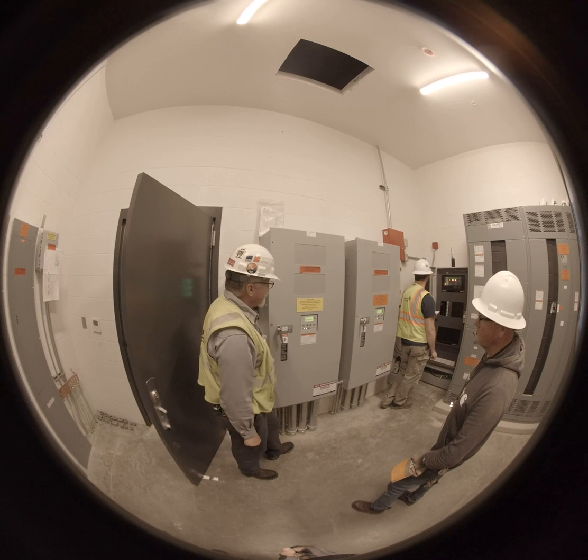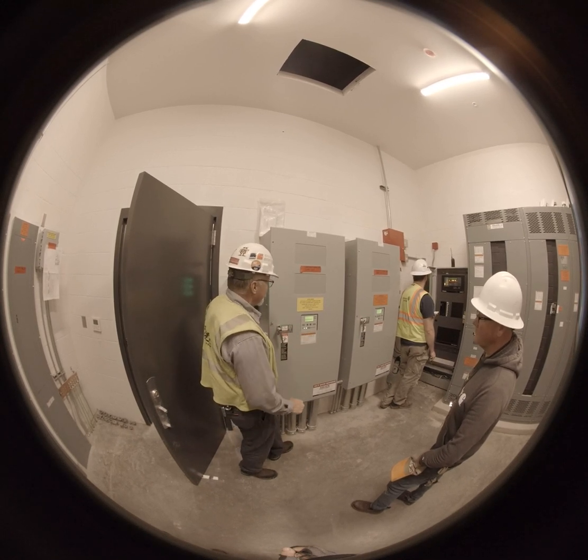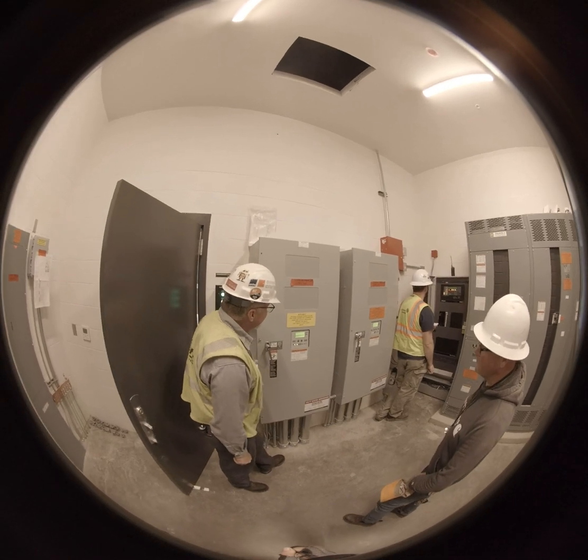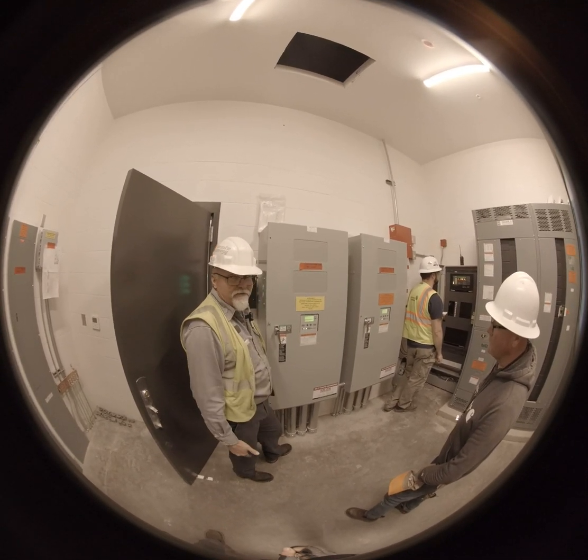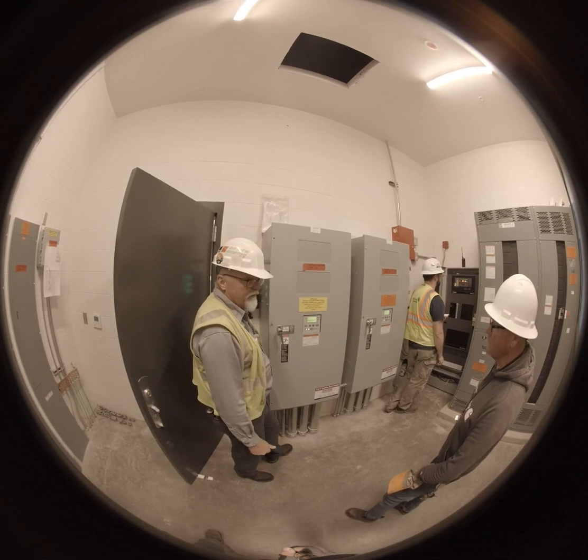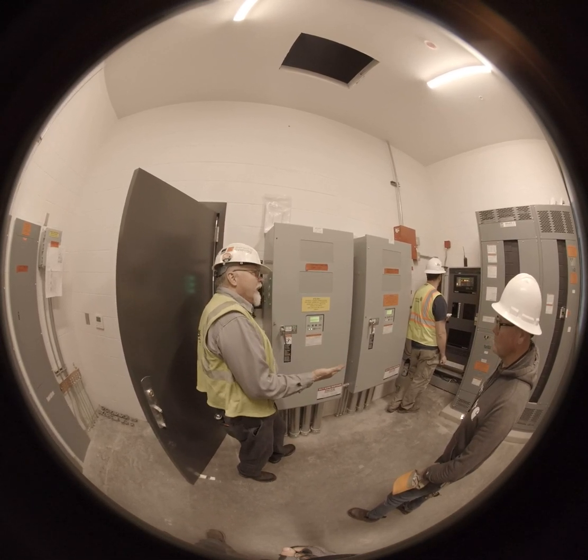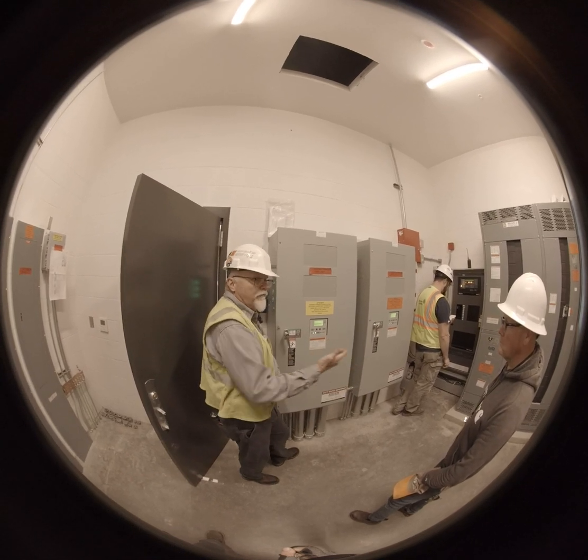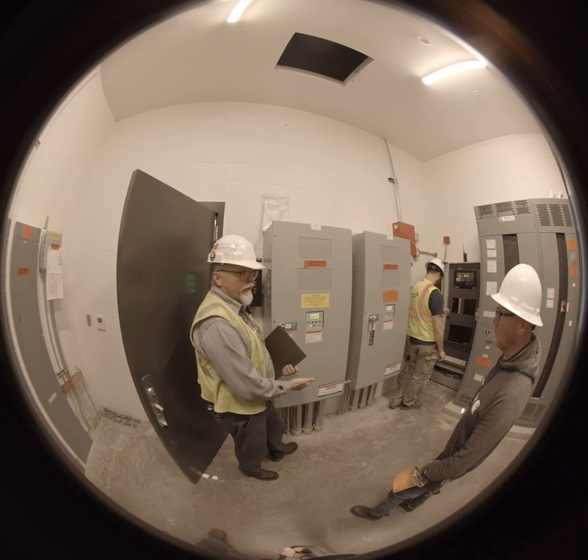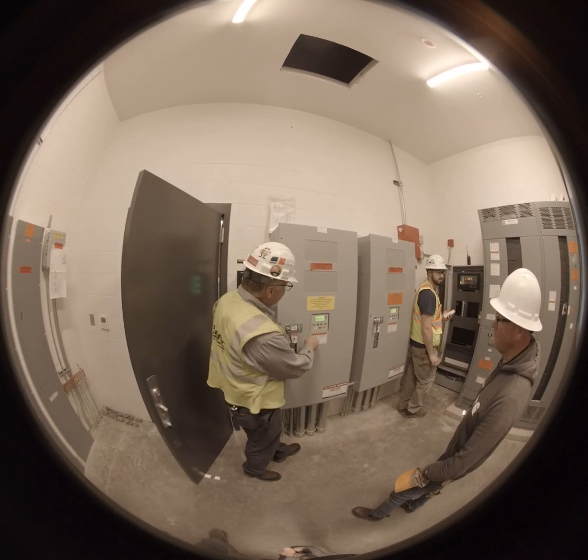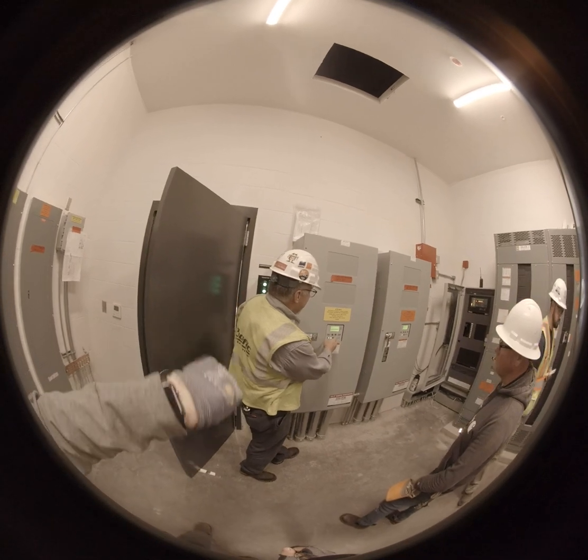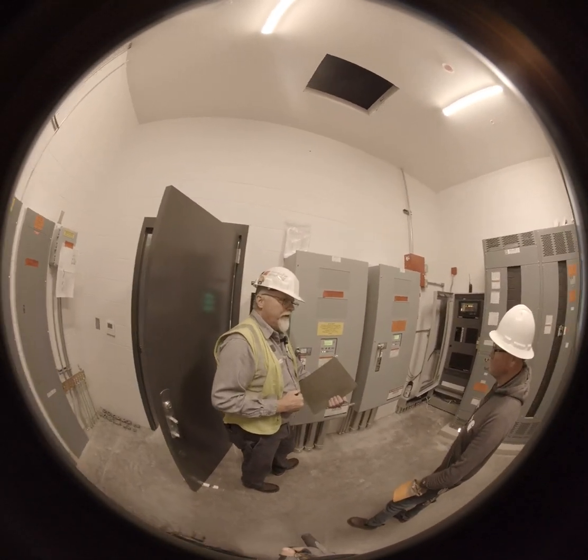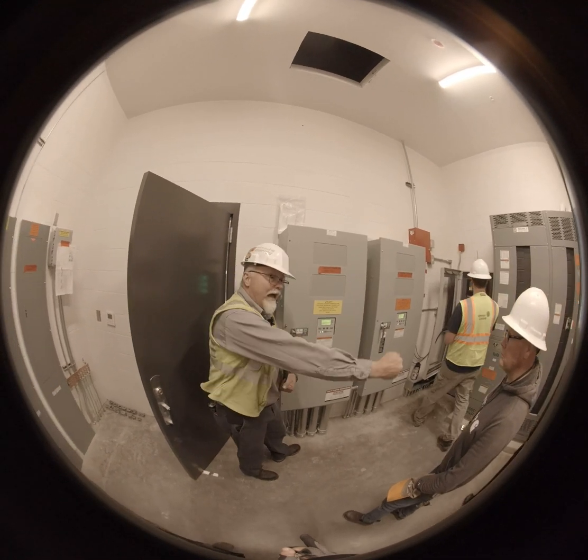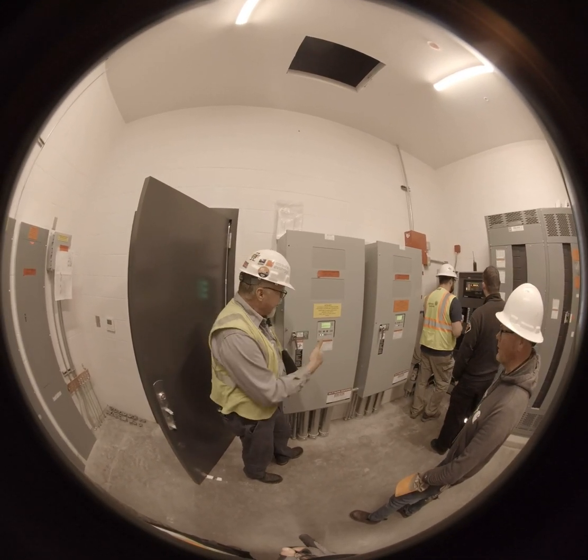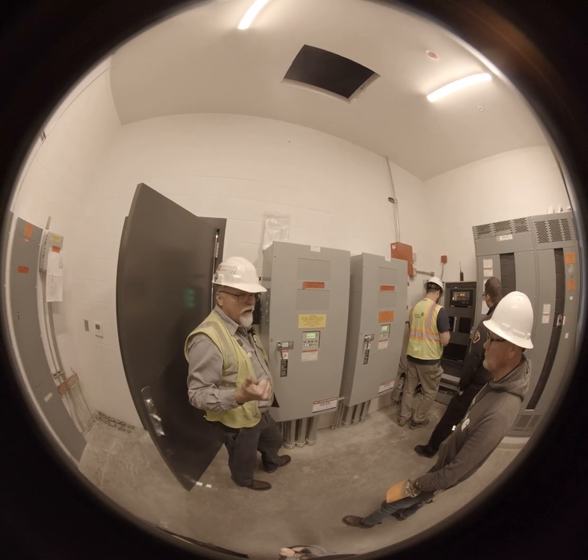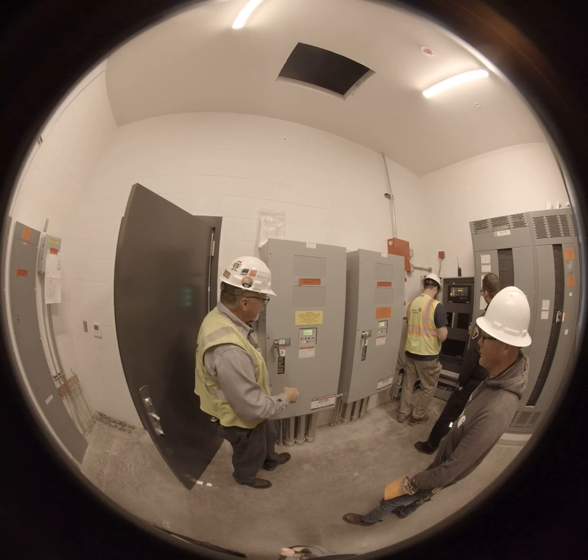Okay? Now, I talked about the elevators. Now we're getting into pre-alarms. Or not pre-alarms, pre-signals, sorry. Normal to emergency pre-signal is set at 20 seconds. I'm assuming it worked. They tested, I guess, on Friday, and nobody said anything about it. But the idea behind that is it should give them enough time to do whatever function they want on the elevator before it actually transfers. So they've got it set at 20 seconds. Post, in other words, after the transfer, you can also set it up before you start the operation again on the elevator. And that is set at 0. The elevator company did not request a post transfer. They just wanted a pre-transfer.